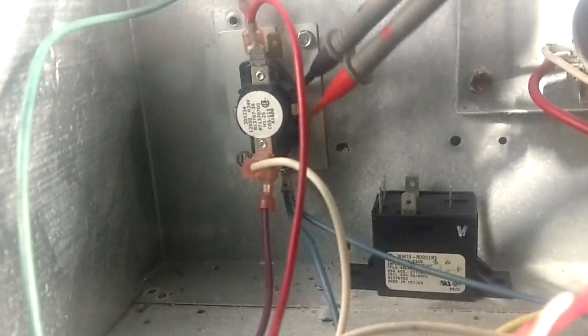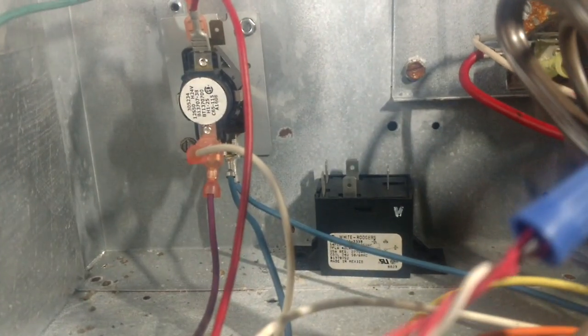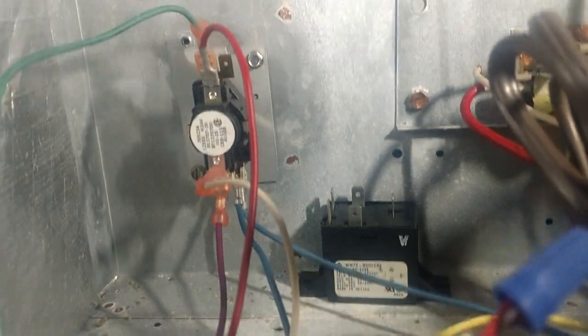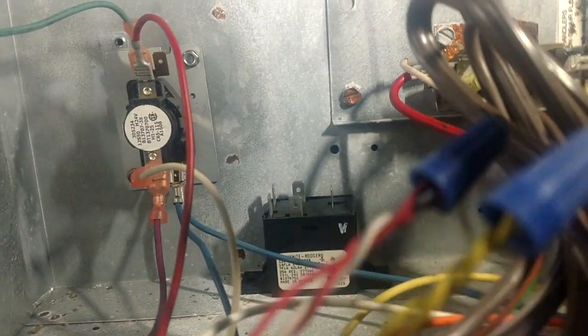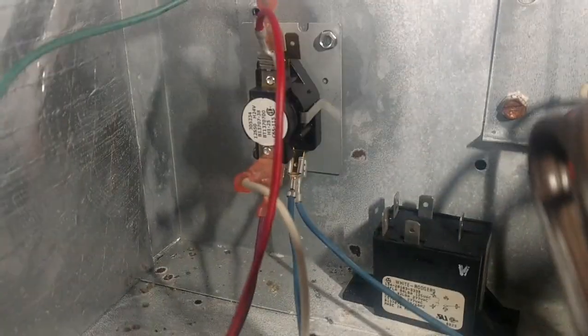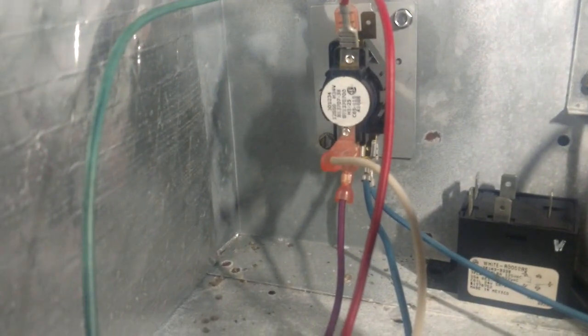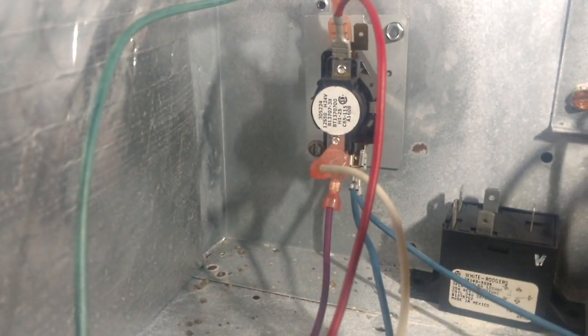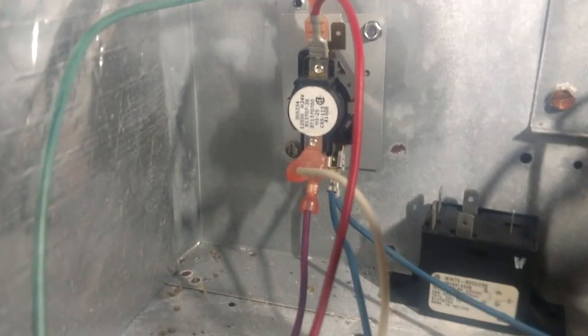Now we're going to check the bottom side of this relay. That kind of looks like a heat sequencer, but that's just something that Goodman has used over the years. That goes all the way back to the Janitrol days. But you see the green wire on the top is going to be the 24 volts, and the blue wire is going to be our common. So we are just going to go ahead and verify that we do have 24 volts on that coil, which we do. So now we know that that relay is being told what to do, and either it's not doing anything or the motor is bad. So now we need to verify that.